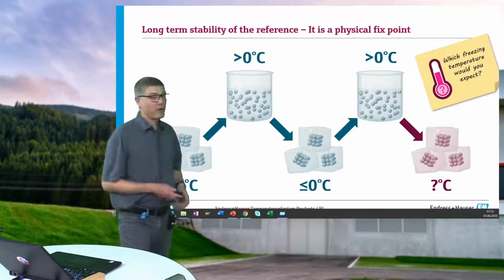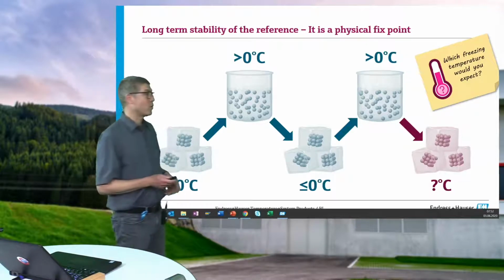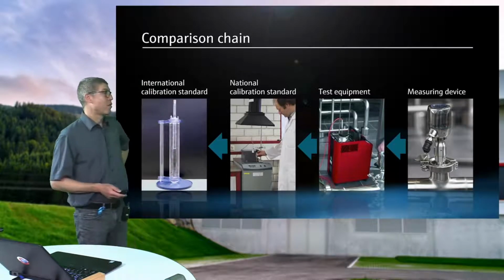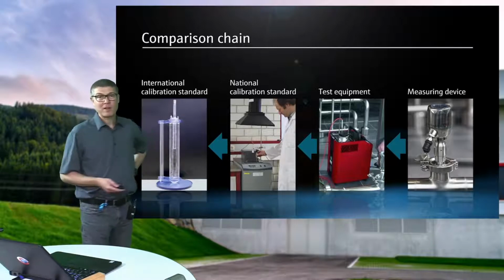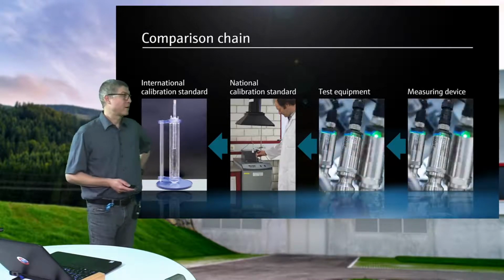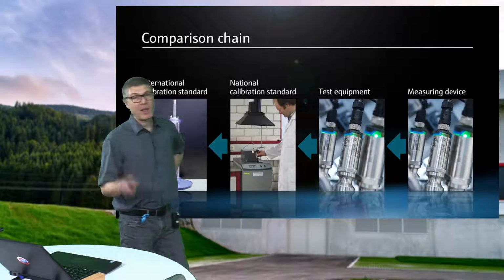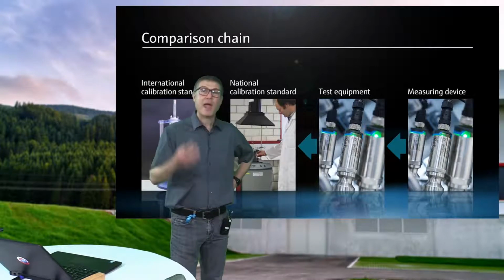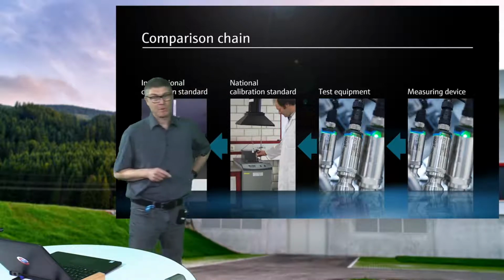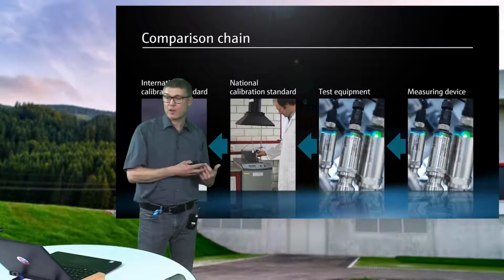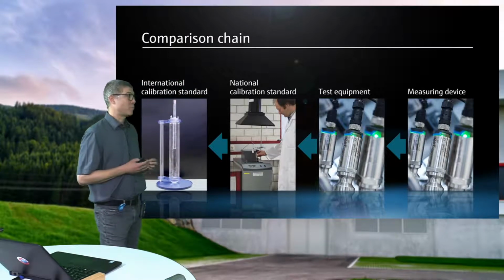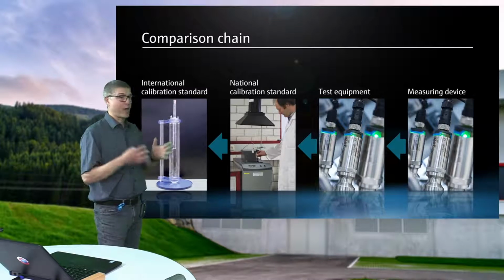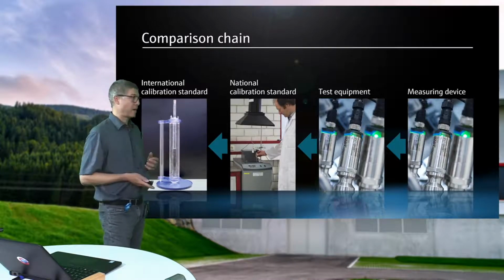Okay, good. So this is the effect we are doing with the Trust Sense. The comparison chain is still active because we have calibrated the Trust Sense, the sensor, and the behavior of the crystal in our accredited lab. So the traceability chain is still active, and it's possible to have traceability on the certificate.